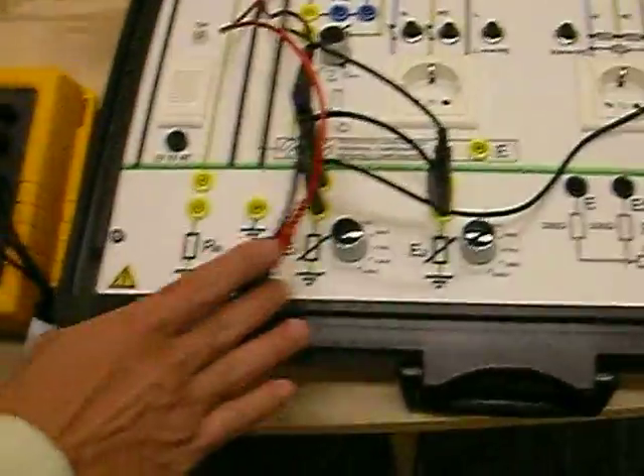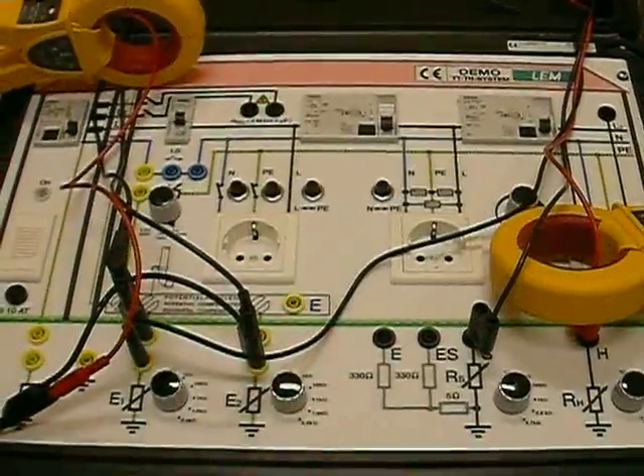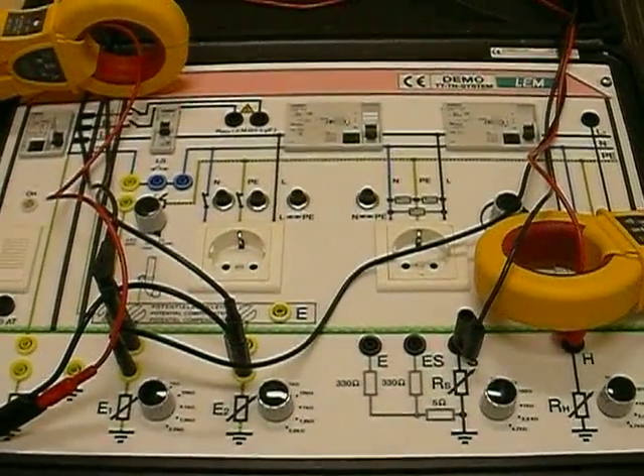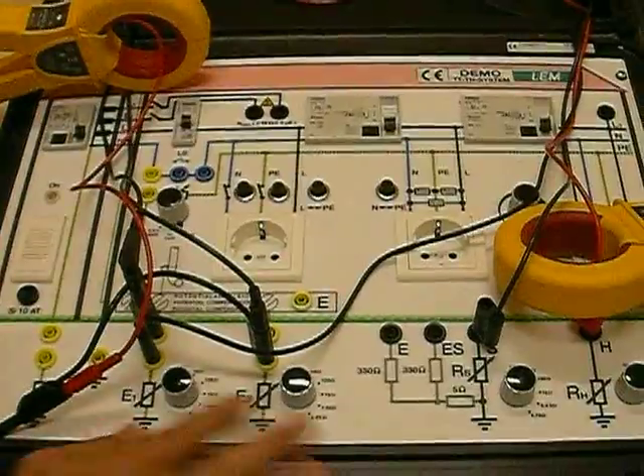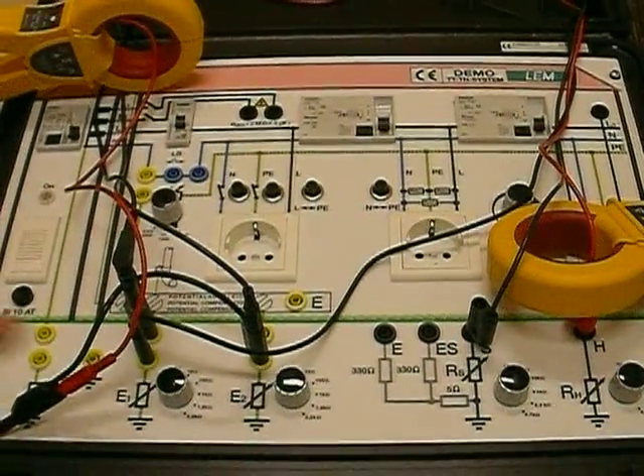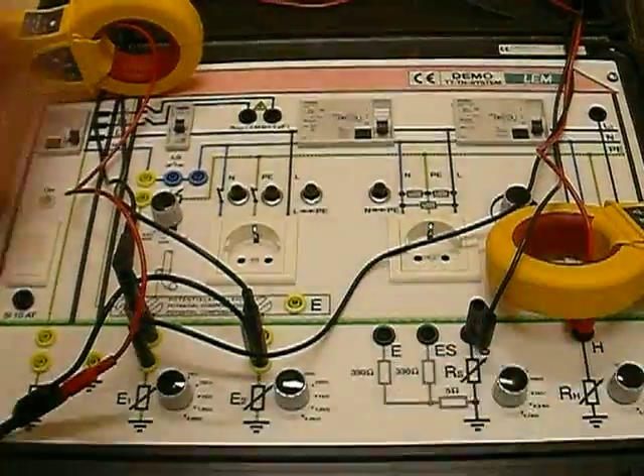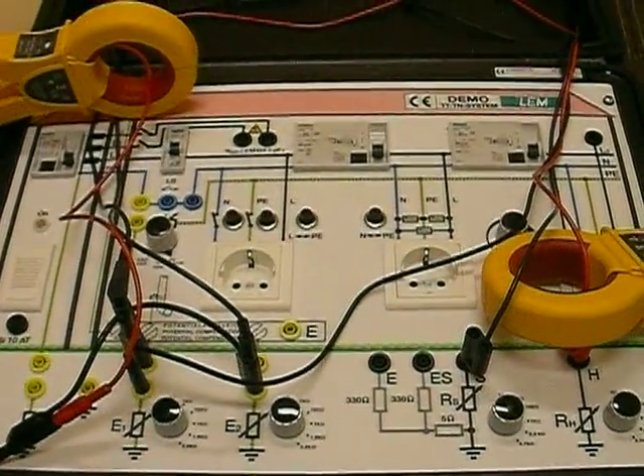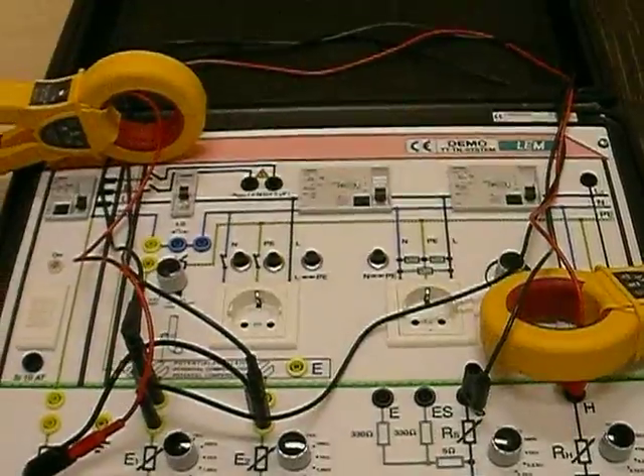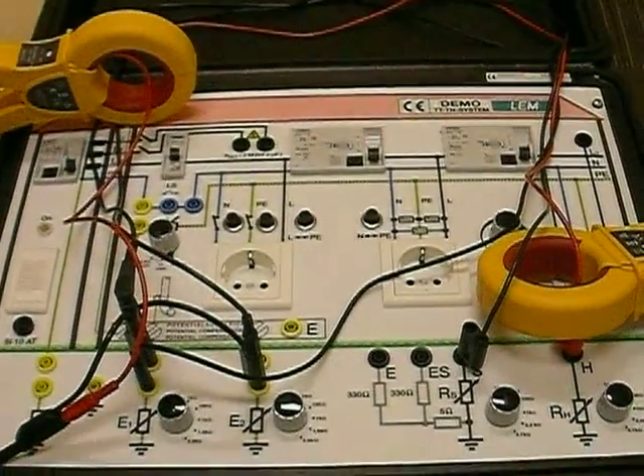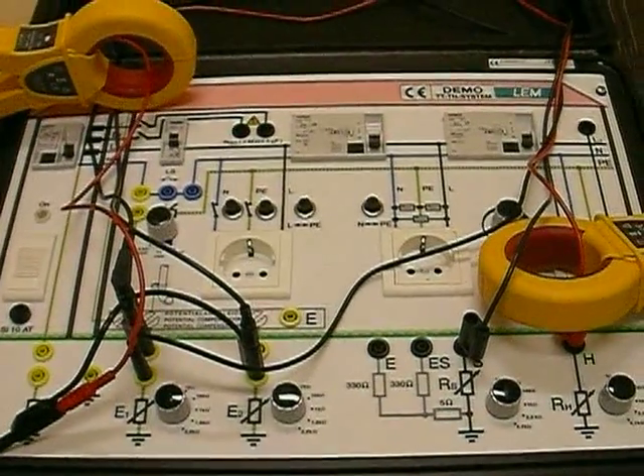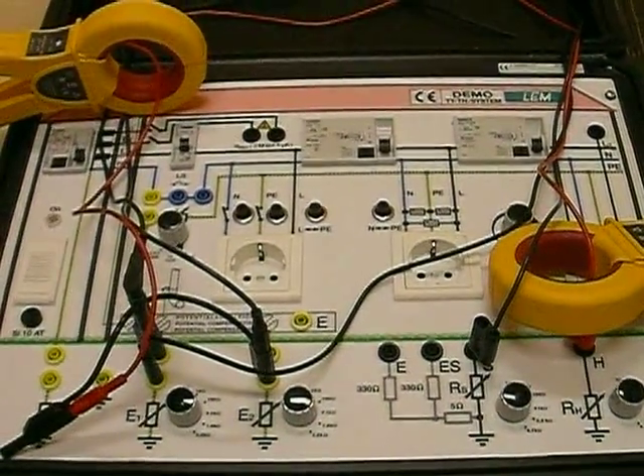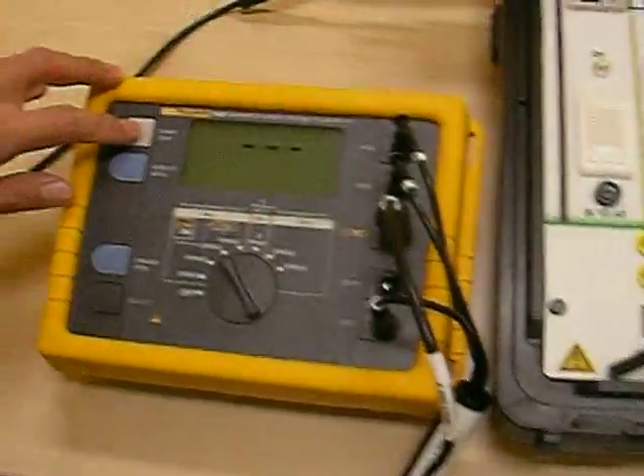Now looking at the multiple grounding rods. Usually in such a system, their grounding resistance should be typically about the same for every one of them. Except now we want to find out if any of these happen to vary due to deterioration in the connection because of either corrosion or loosening over time. So to do this, we are able to now do the test.